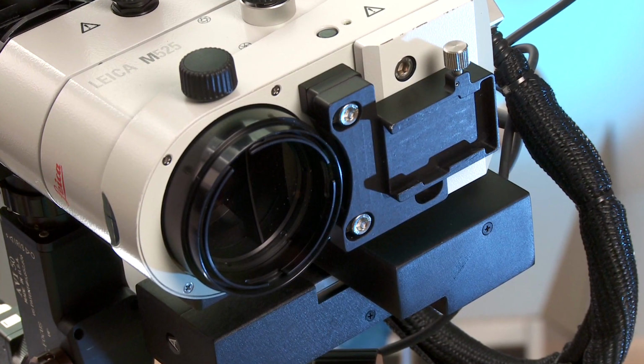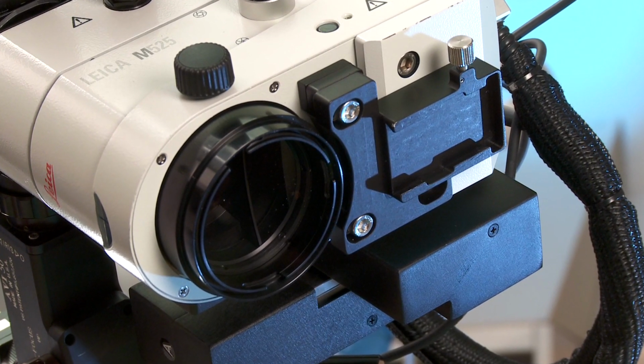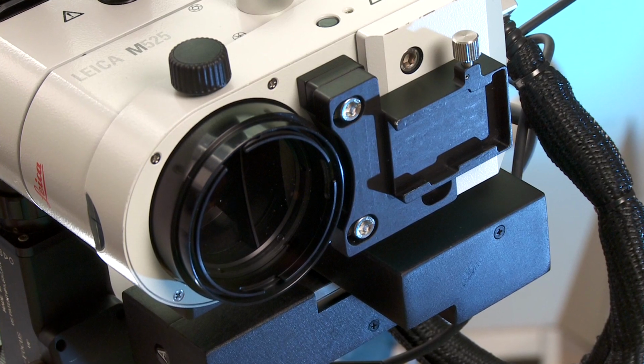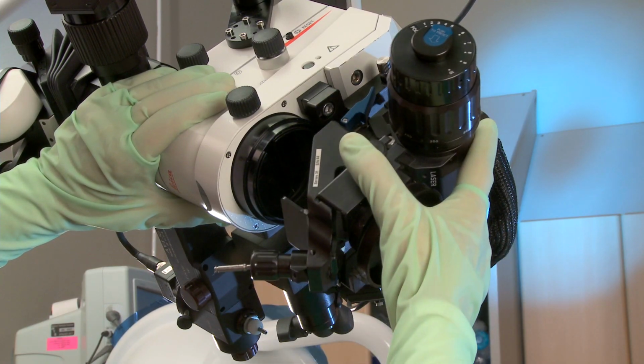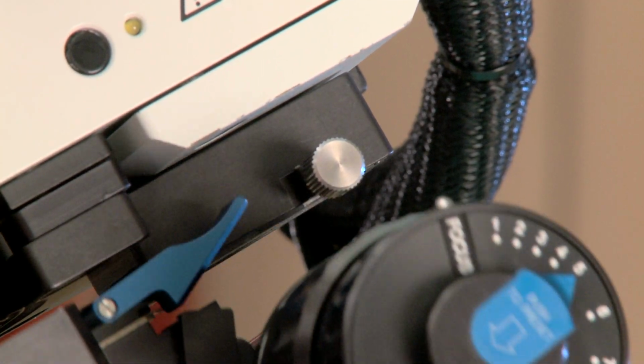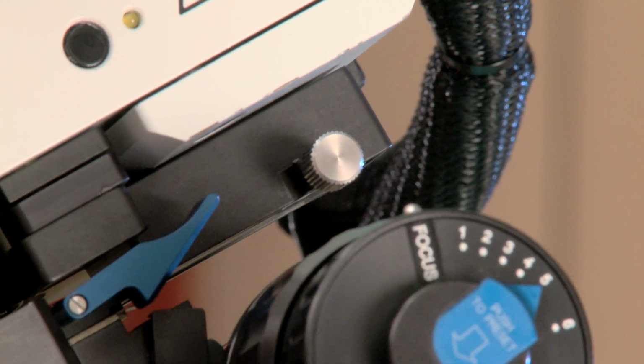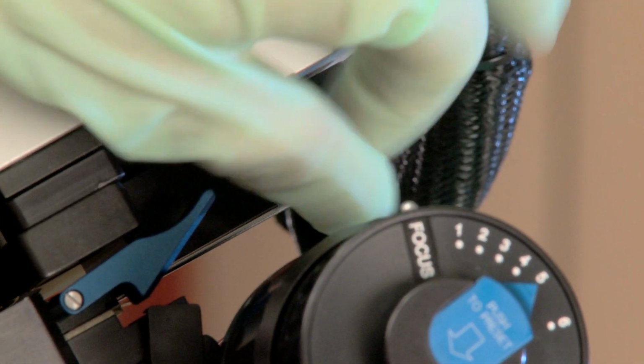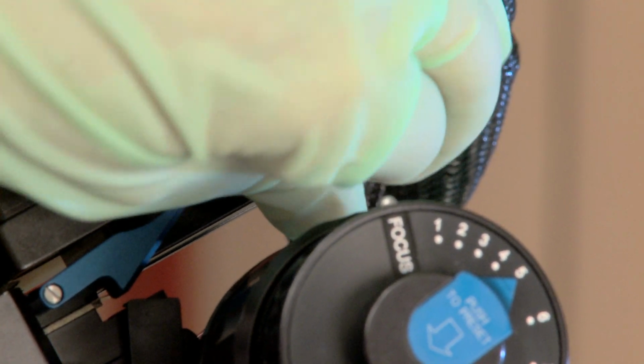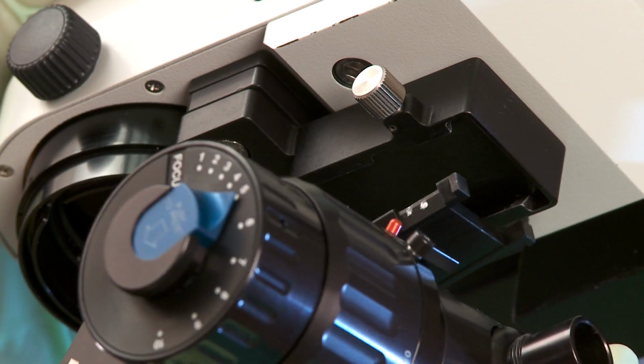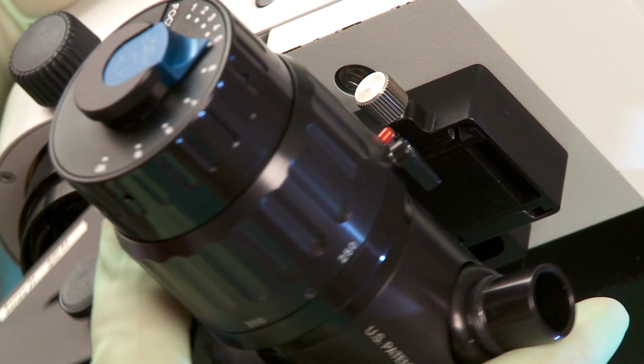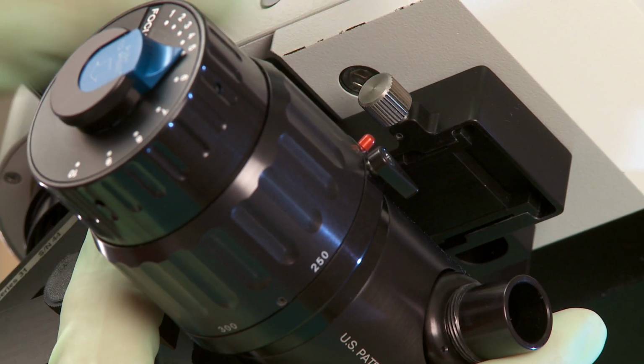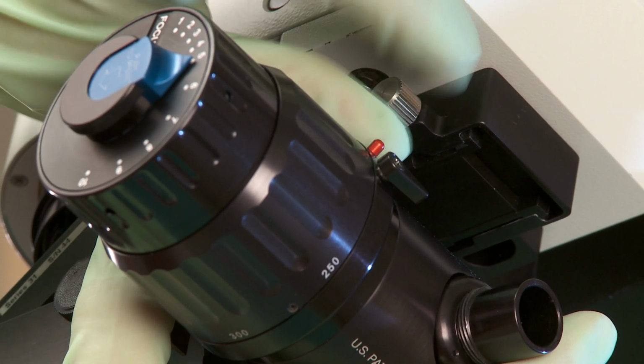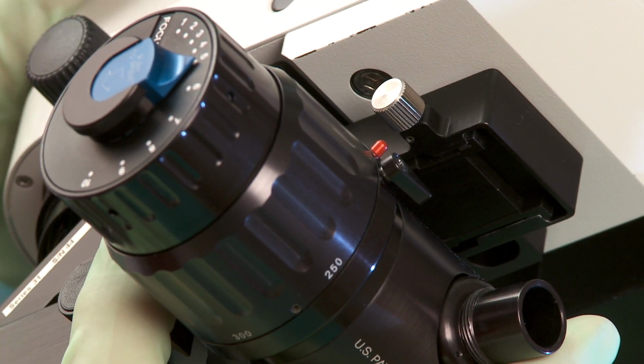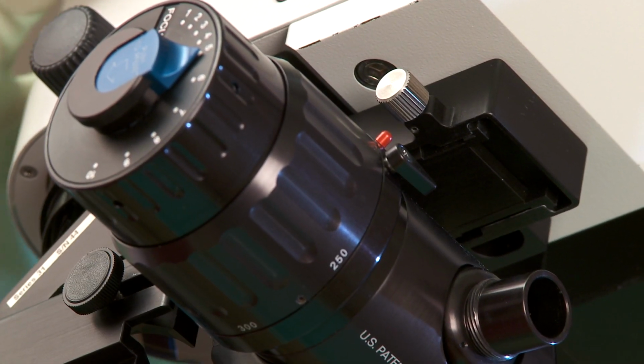The mounting side of the micromanipulator is flat, so that it can attach to the microscope. It has a dovetail mount which inserts into a Luminous-supplied bracket, installed onto the microscope above the objective. Microscope brackets are specifically designed for common brands of microscopes, such as Carl Zeiss and Leica. Once installed, the bracket can usually remain on the microscope.